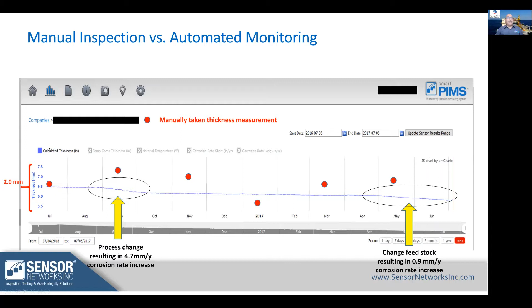Our sensors can be divided into wired, where frequent measurements are required but wireless infrastructure is not available — note that although data is collected manually, it still offers the advantage of moving data collection to an easily accessible point — and wireless, where there is no need to access the sensor after commissioning, as data is sent by communicating to a gateway, for instance via a long-range radio network, or using the existing public mobile network for automatic data transfer to internet cloud-based analytics software. Wired or wireless sensors can be installed permanently or temporarily, giving the engineer the chance to decide case by case what the best option is.